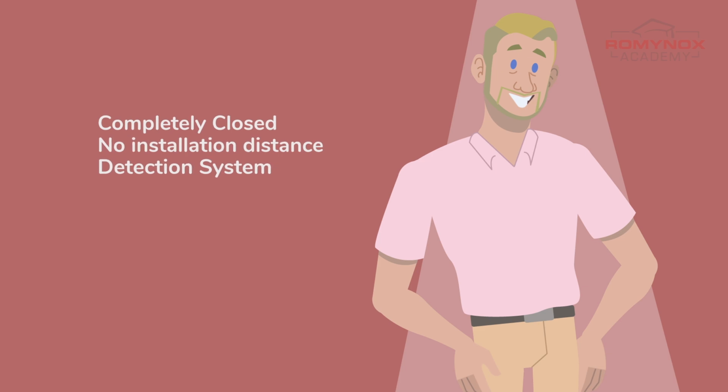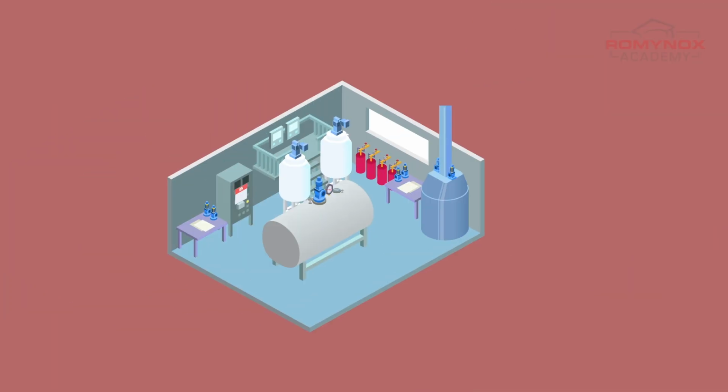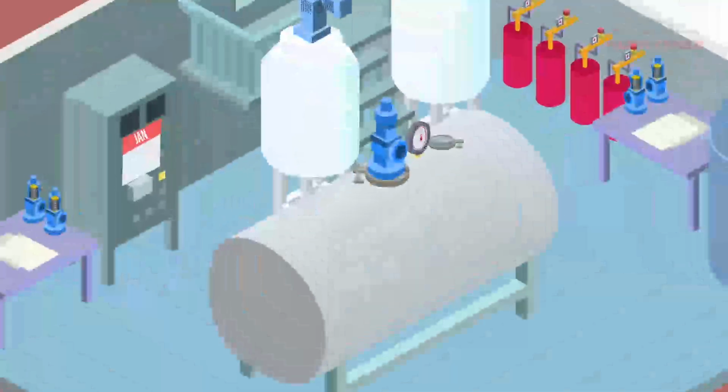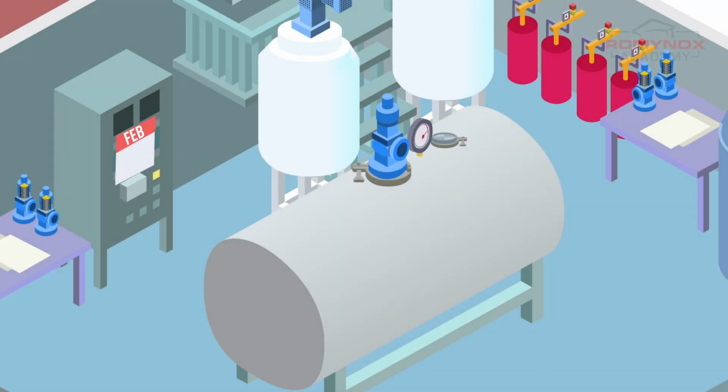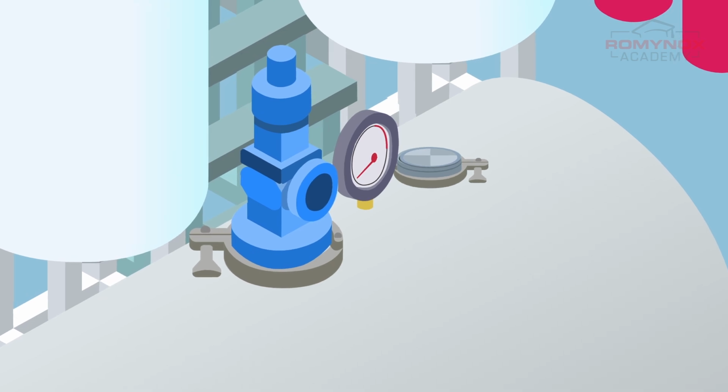If you want to, you can use the bursting disc in combination with a disc indicator. A bursting disc can be pressurized up to 95% of the preset bursting limit without any leakage or wear. Its preset value will not change over time, so the disc is maintenance-free. A bursting disc can simply stay in place to be readily replaced in the event of an incident.